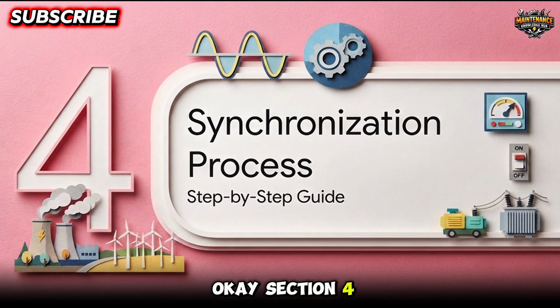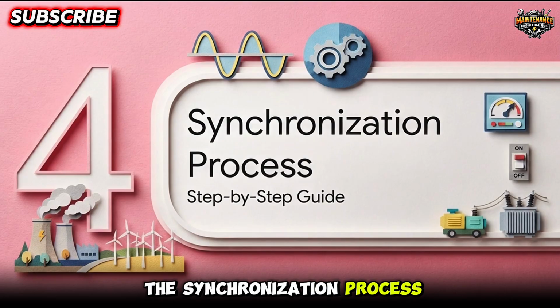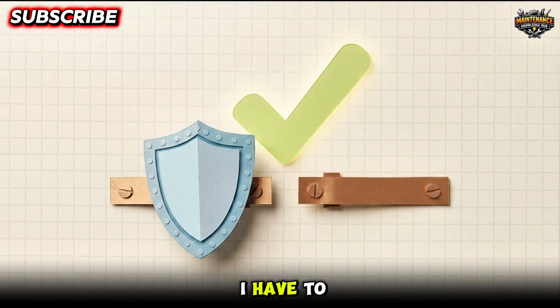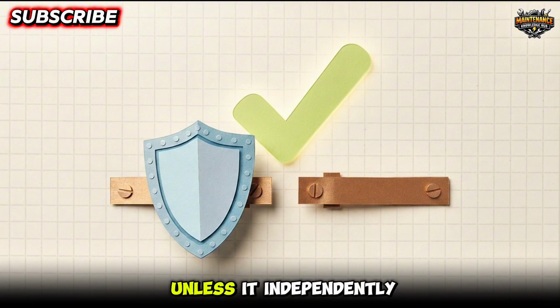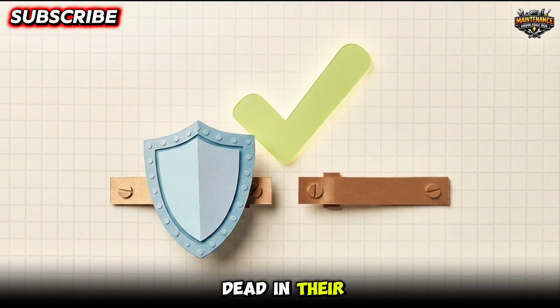Okay, Section 4. The synchronization process. Before we do anything else, I have to introduce you to the real unsung hero of the power plant, the ANSI 25 Synchronism Check Relay. Seriously, this thing is the ultimate failsafe. Even if an operator, or an automatic system for that matter, sends the command to close the breaker, the ANSI 25 relay acts kind of like a bouncer. It will physically block that command unless it independently verifies that the voltage, frequency, phase sequence, and phase angle are perfectly safe. It literally stops catastrophic mistakes dead in their tracks.